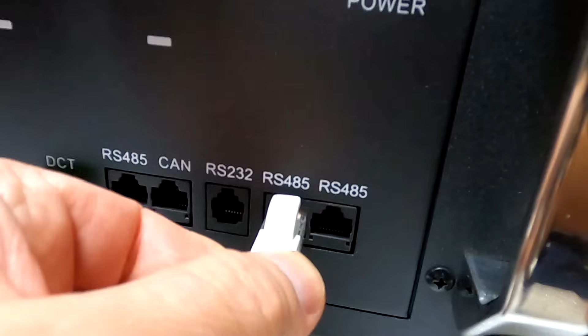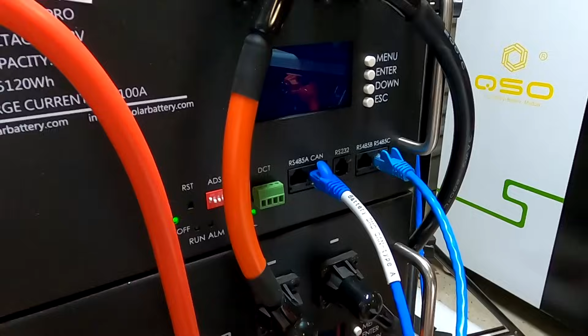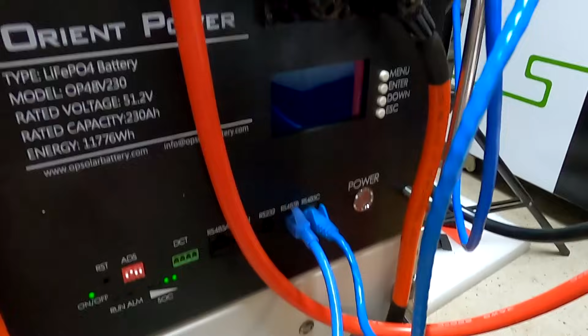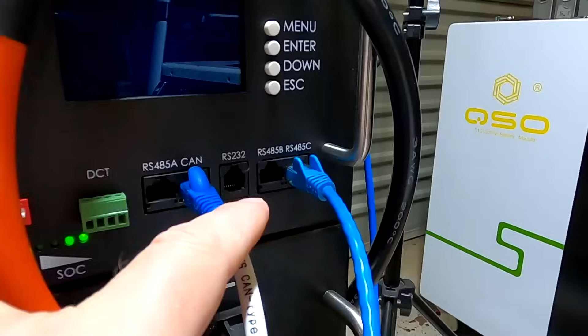And then we can just take a normal LAN cable, connect this here to the RS485. And now we can connect this to any free RS485 port here on our battery system. So we've got one free down here at the Orient Power BMS, or we've got another one free here at the master BMS at the top. So if you plug this into the top, for example, we should see that 4 batteries are online at some stage. There it comes.